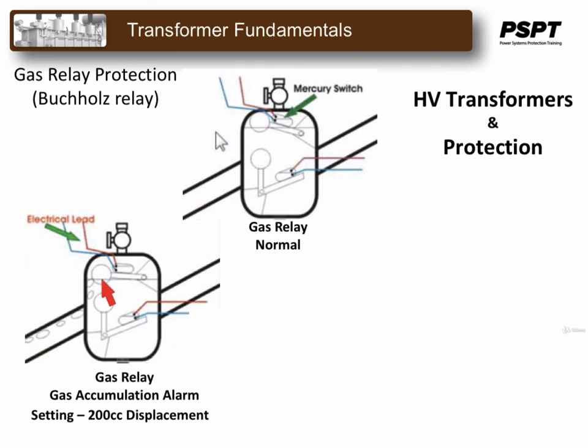Depending on the design of the Buchholz relays, there could be a second float, and it is designed to detect slow oil leaks in the oil of the transformer. And if the oil level drops too low, in this case, it would initiate a trip of the transformer.